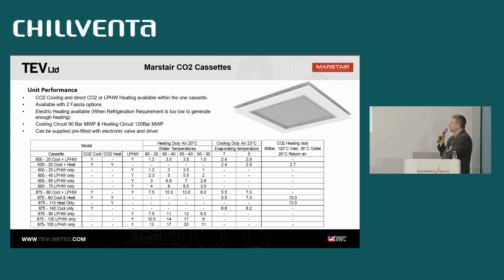In terms of each of the options that we have, on the cooling side we work at 90 bar max working pressure, and on the heating side we have 120 bar max working pressure. And if you want to, we can do pre-fitting of valves, depending on what type you want to go for on the cooling side.